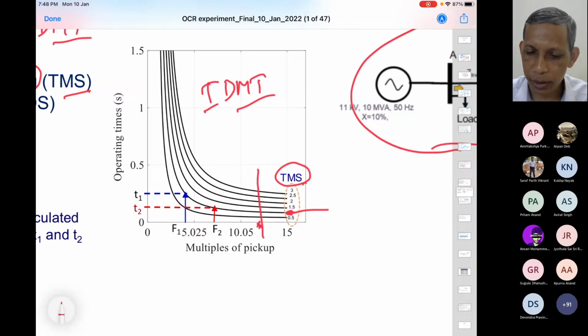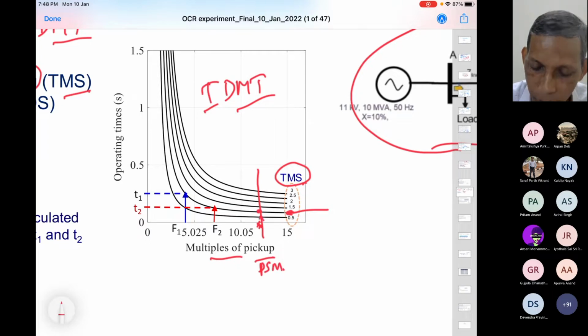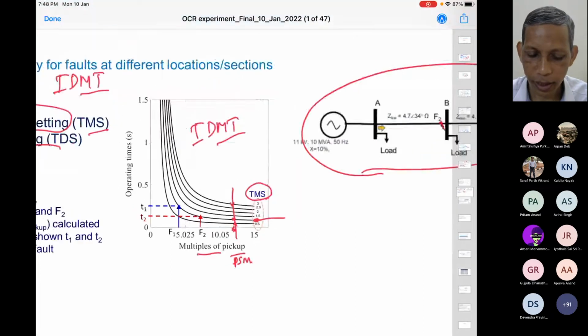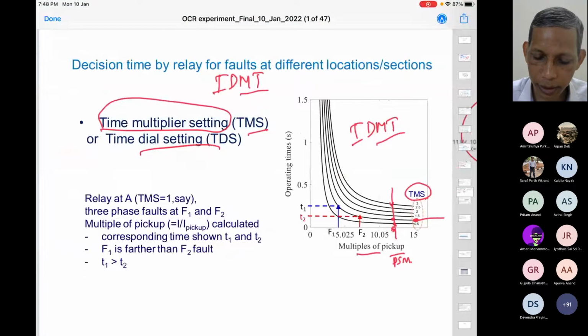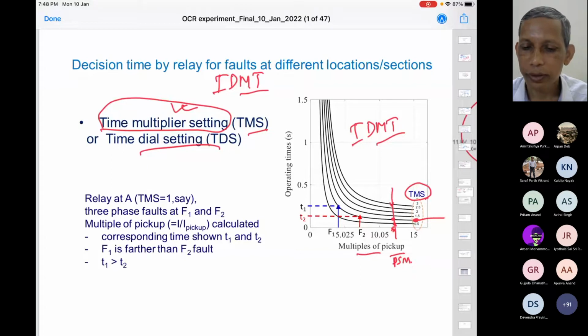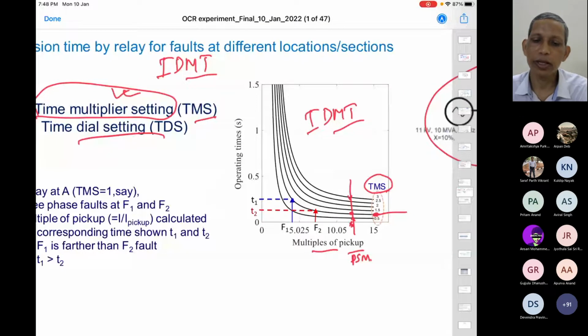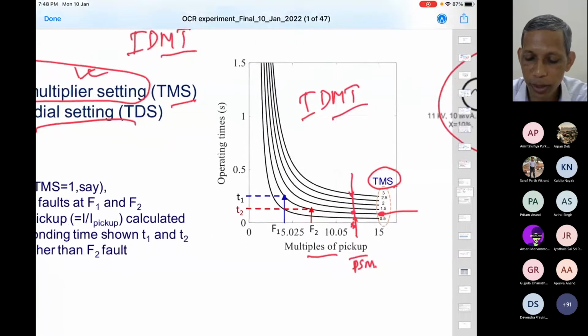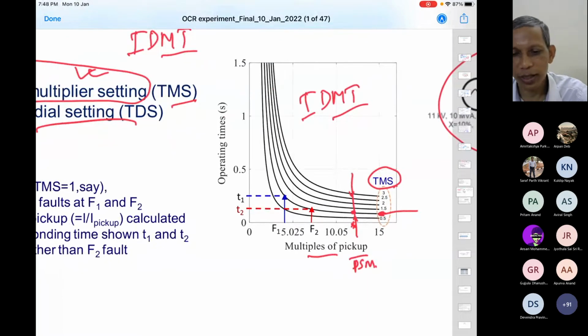At the same current level divided by the pickup setting, the same PSM, the multiples of pickup, you see here, for 1, this is the time, for 0.5, this is half, and for 3, three times. That control is also there with the IDMT characteristic, and that is what we call the time multiplier setting. I'll show in the formula also how this can be used for the relay characteristics variation. These are the different options available in the numerical relay platform. You can change the corresponding characteristic curve. Each one is a characteristic curve. You have to pick which one will be useful for a particular location and particular application.